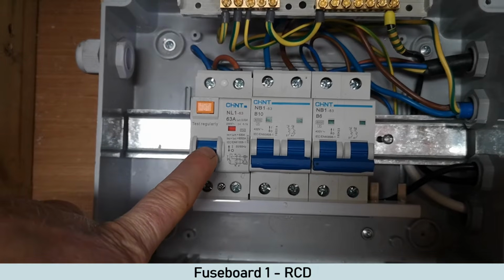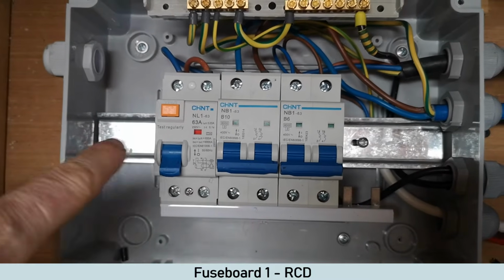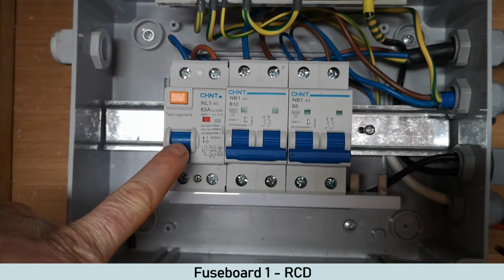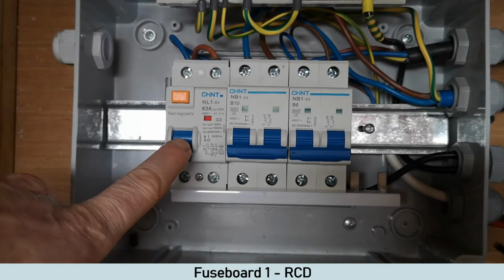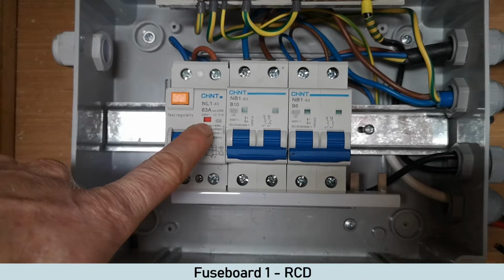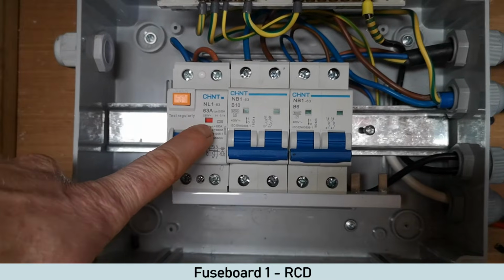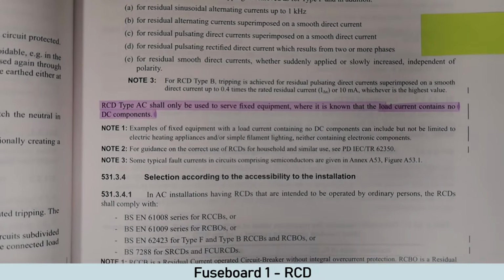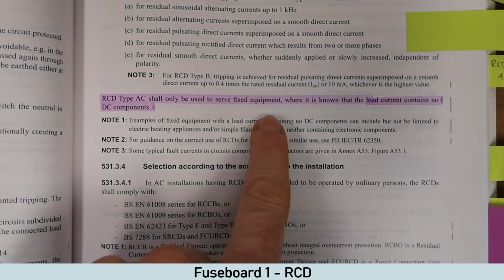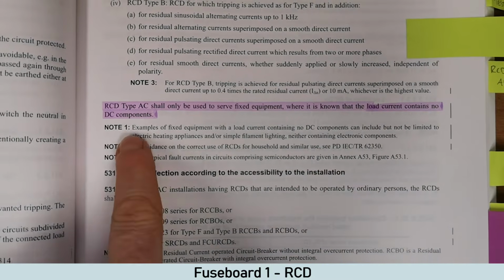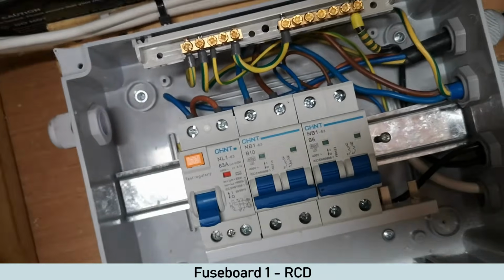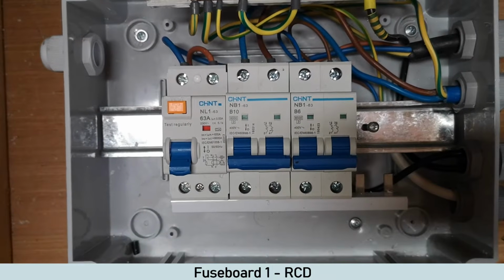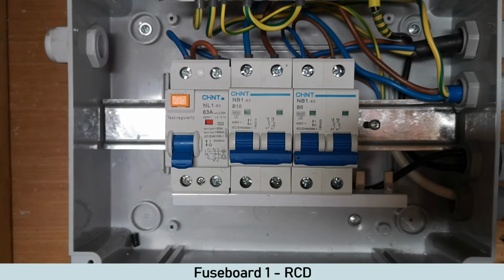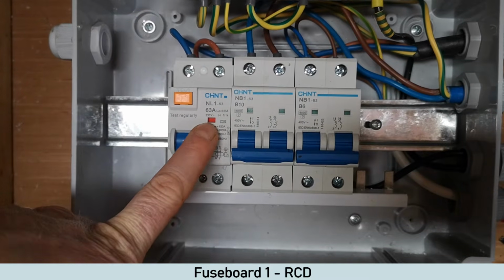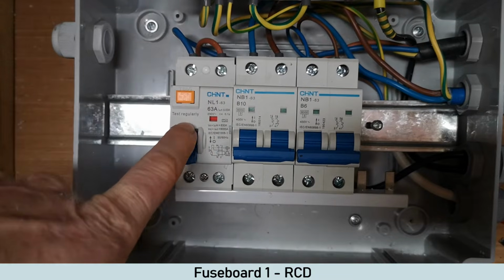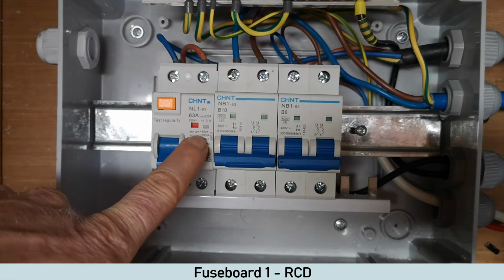Now generally RCDs are type AC. What AC means is it's supplying AC circuits basically, which is what we have here. However, with an AC, it does state in the regs that you should only use type AC RCDs if there are no DC components plugged in. So here it is. Type AC shall only be used to serve fixed equipment where it is known that the load current contains no DC components. Nowadays, most stuff you plug in, like a telly, a laptop, anything like that, has a DC transformer basically. So you'll find that AC RCDs are becoming obsolete. So in a camper van, you must have a type A RCD and not a type AC.